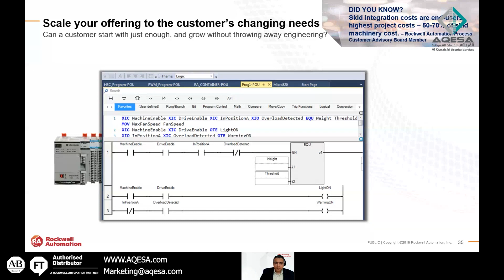A new thing that people are using: you know that Compact Logix and Control Logix are both programmed by Studio 5000, so you can change the controller, take a copy, and so on. What's new is that you can copy these to Connected Component Workbench. So you can copy and paste code made for Control Logix or Compact Logix into Connected Component Workbench easily, reusing or sharing ladder logic between Connected Component Workbench and Studio 5000.